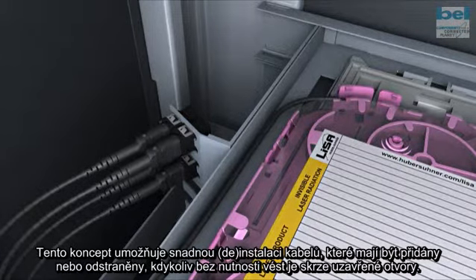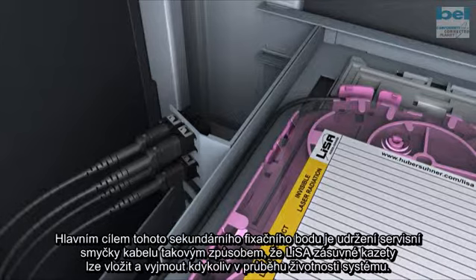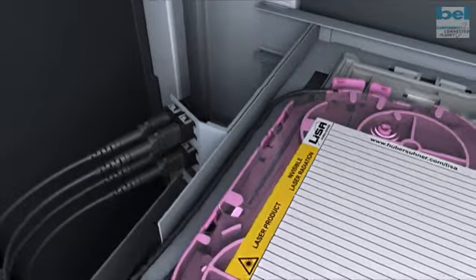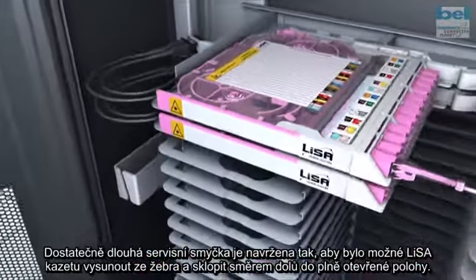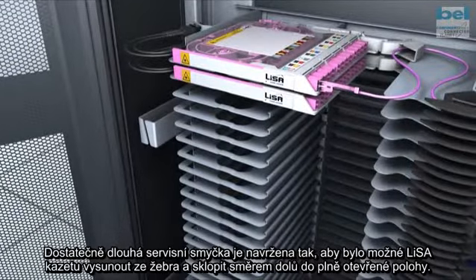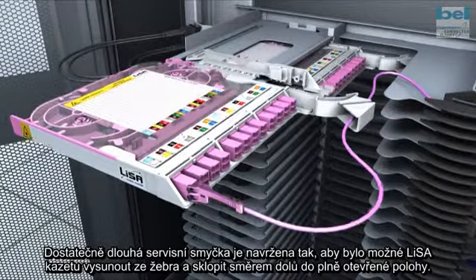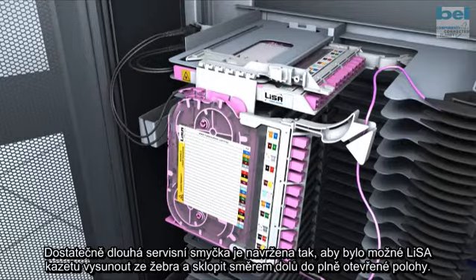This open-sided concept allows cables to be added or removed at any time without the need to route them through closed holes. The main purpose of this secondary fixing point is to maintain a service loop of cable so that LiSA fibre trays can be inserted and removed at any time during the lifetime of the system. Sufficient service loop is afforded so that the LiSA fibre tray can be slid out from the tray unit and hinged down to its fully open position.